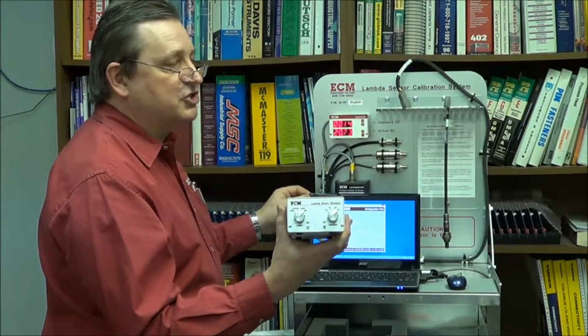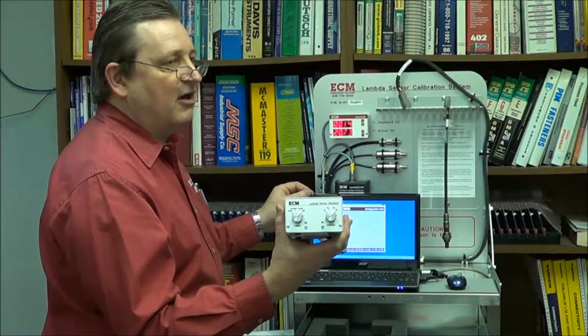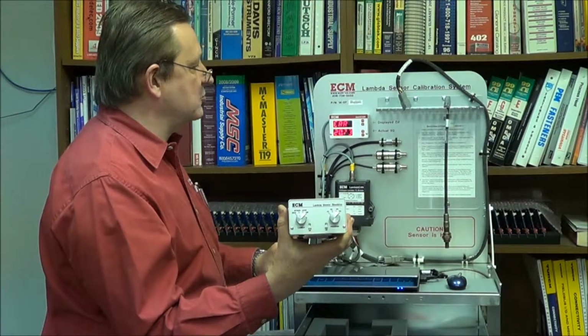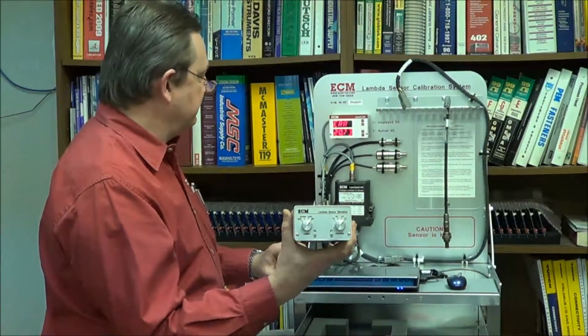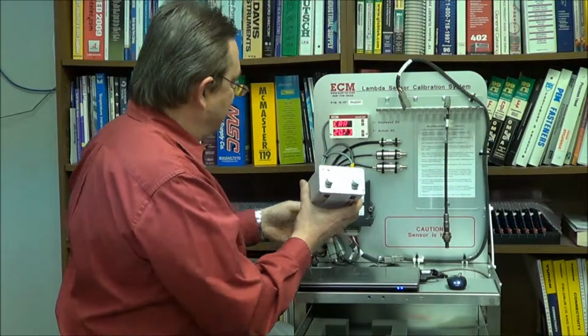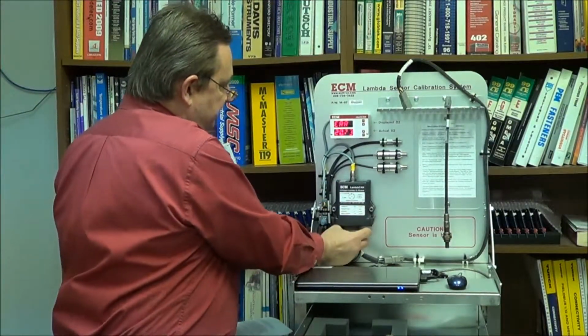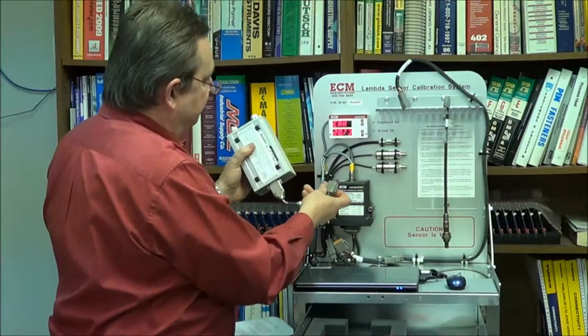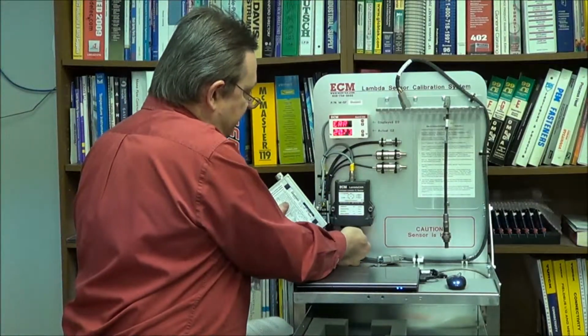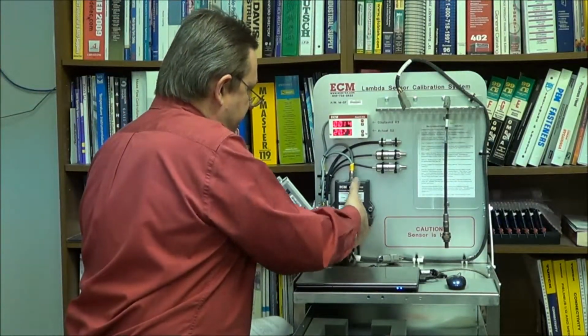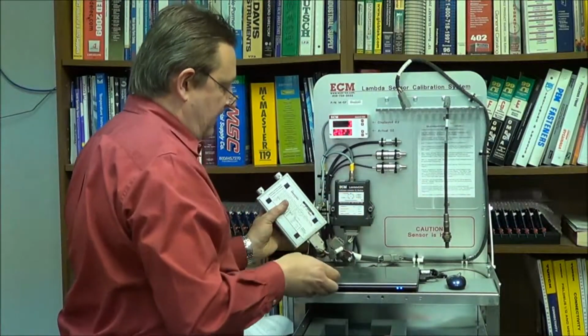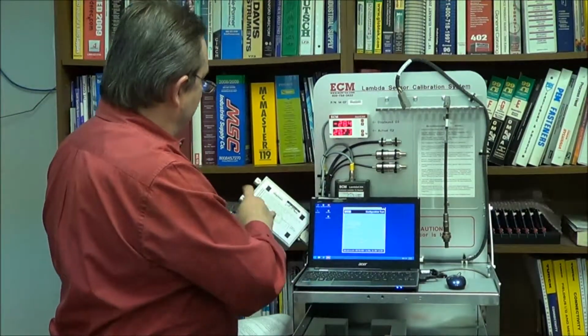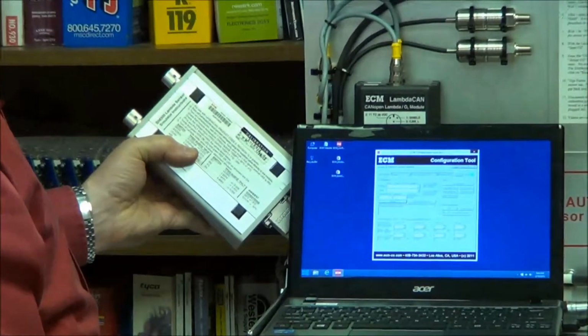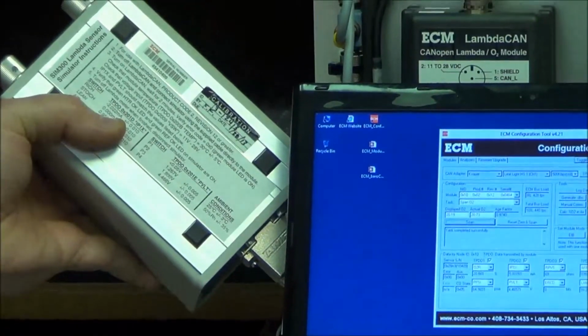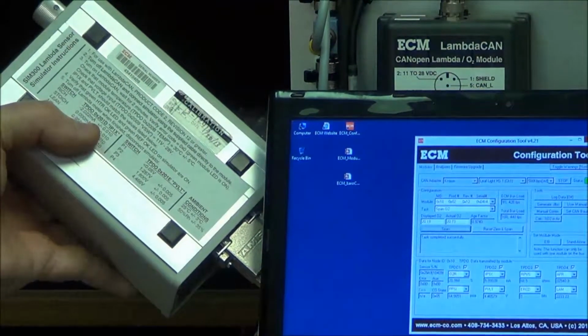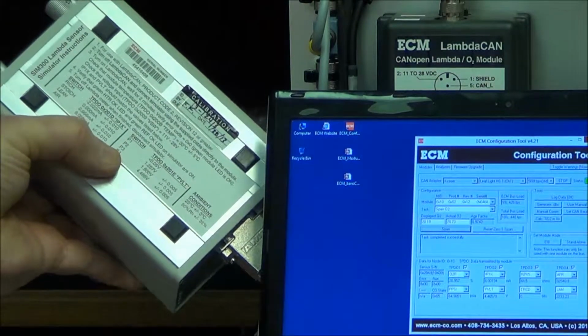You don't have to check out the LambdaCAN very often. I suggest once a month with this system. To check it out, it's really simple. You just pull out this connector and plug it in and follow the instructions on the bottom of the device. Okay. You have to look on the PC. So this device outputs 4 currents, simulating 4 different stoichiometries with the sensor, and 4 pressures.